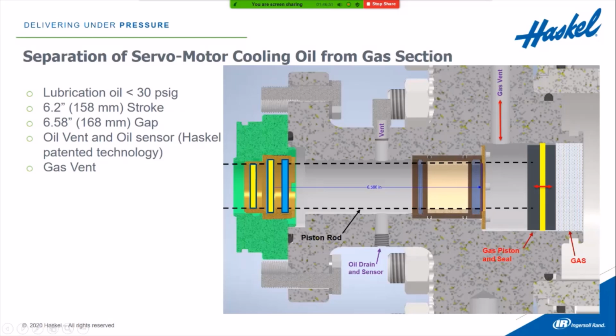This represents the gas piston with a seal on there. And this section right here would be our process gas. It might be something like helium or nitrogen. Behind this piston, we have a gas vent. So any gas that does leak across the seals on the piston will escape to atmosphere through this vent. Plus, there's a constant movement of air through this vent as the piston goes back and forth as the volume changes behind the piston. So there's air going in and out at all times.